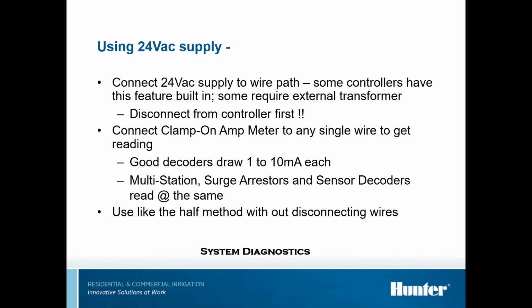Use the half method when you disconnect. That's a bit of a mouthful. If you disconnect the wires in the middle, your milliamps ought to go up and down as you're dropping decoders in or out. And also you can check your current at any point on the wire path. Now remember, be in AC volts, so you have to have the meter in the proper setting.